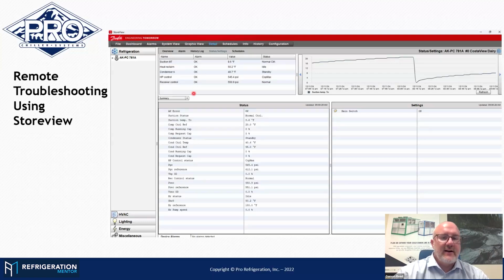The detail view is where, now I'm looking at my status of my suction. I can see obviously a lot more data points. You can select the summary tab and drop down. You can get into safety conditions. You can get into all these different layers of data view points, but you also get the settings tab off to the side. So if you were to drop this menu down and go into like the heat recovery view, for example, you would see the technical data on the heat recovery, and then over on the side, you would see some settings that can be changed by the user.